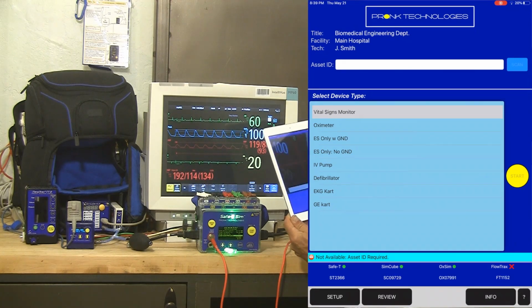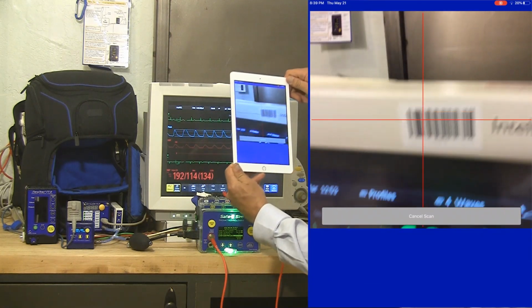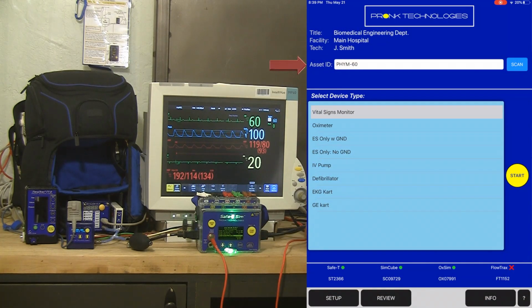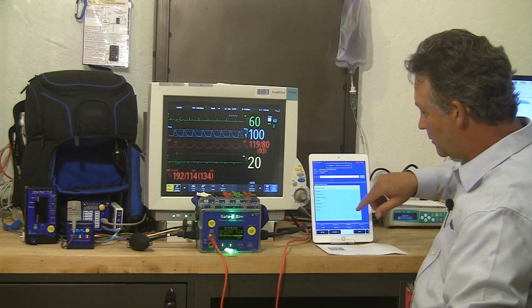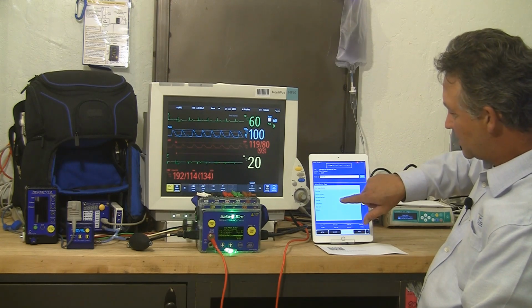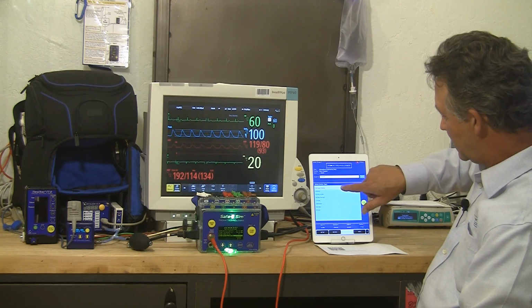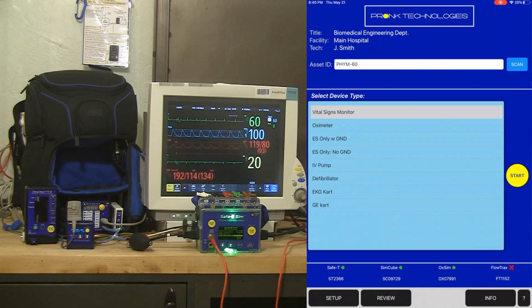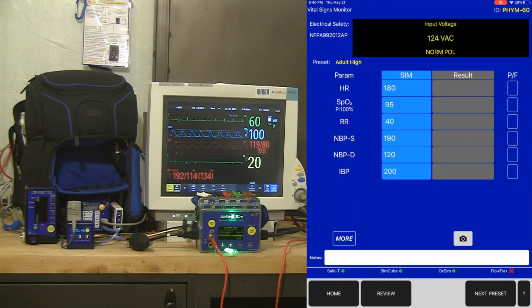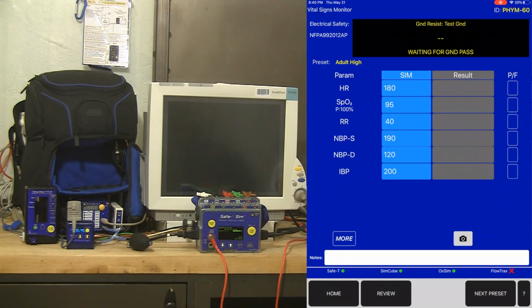I'm going to start with a barcode scan of the device I'm about to test. Get that asset ID tied into my electronic record that's going to build as we go. Then I'm going to select the device type on the iPad. That's vital signs monitors already selected, and hit start. So from here, we've already started controlling our test equipment.